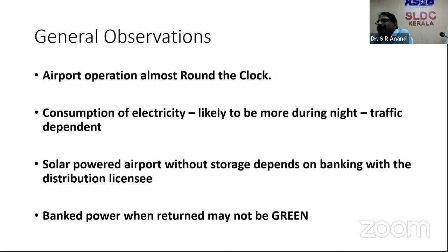Next slide. Now for futuristic suggestions: airports like Bangalore have already indicated they are going for storage. The benefit of internal storage is that it increases the reliability of supply, because without internal storage, in the event of a grid failure or supply failure, the airport depends again on the DG set immediately, going back to grey energy, which is more polluting than energy generated by the grid on a larger scale at a coal-based station.